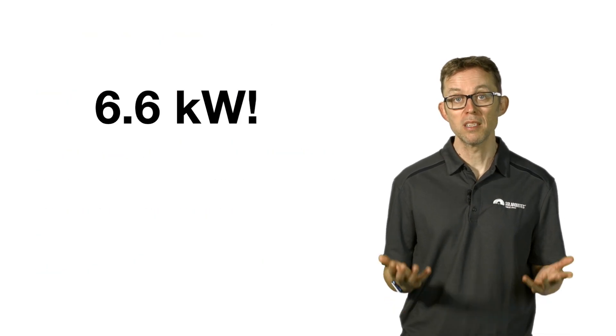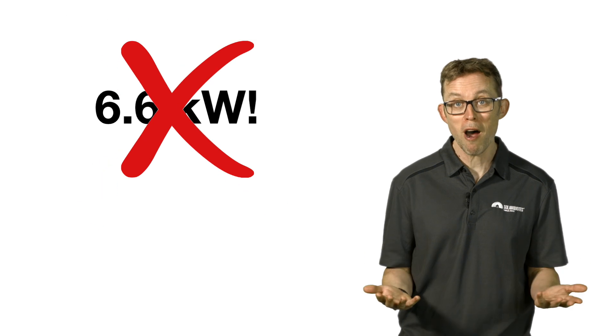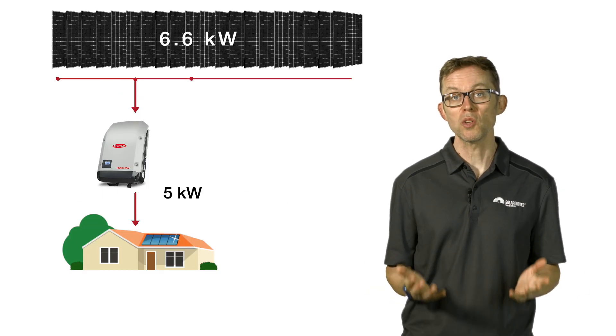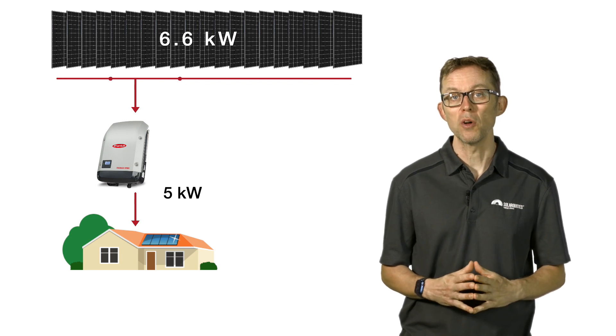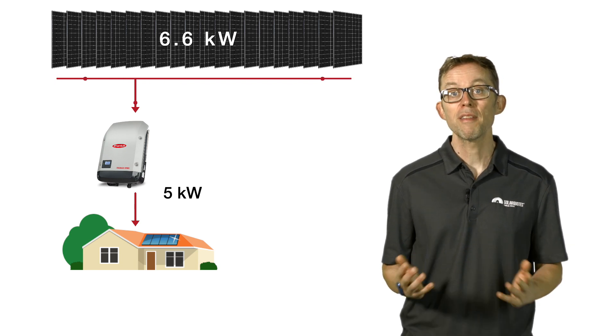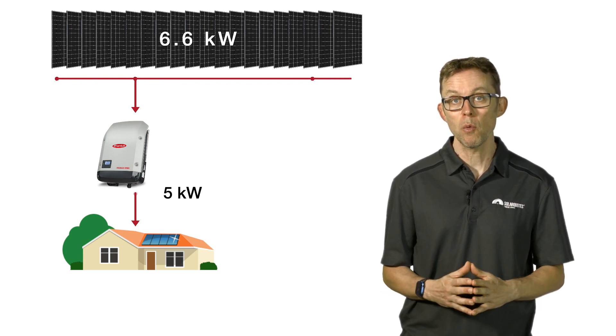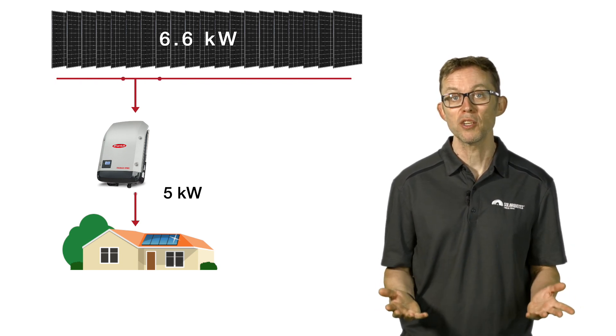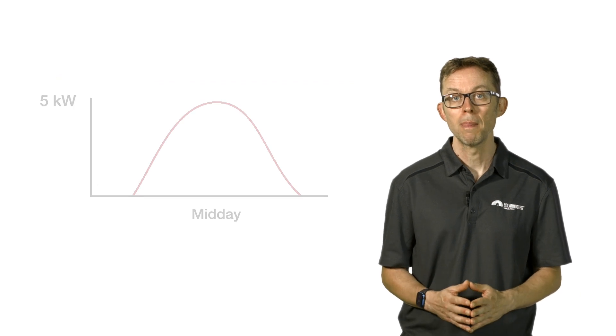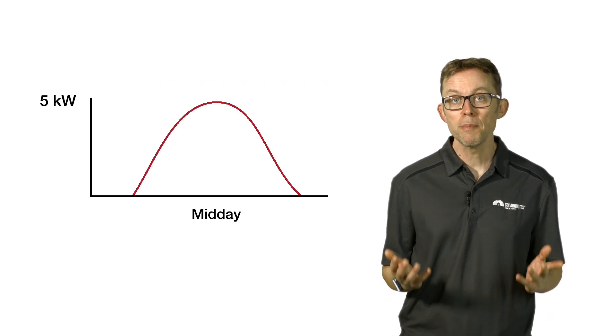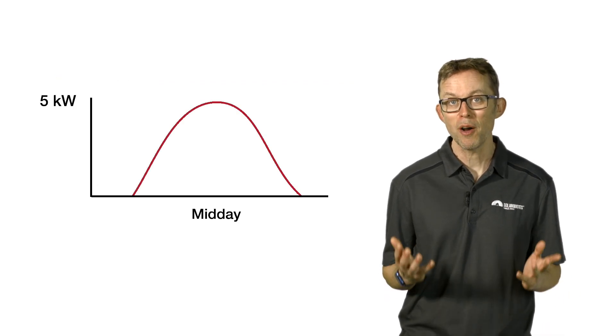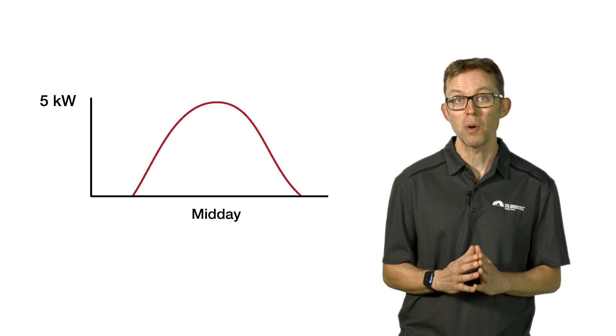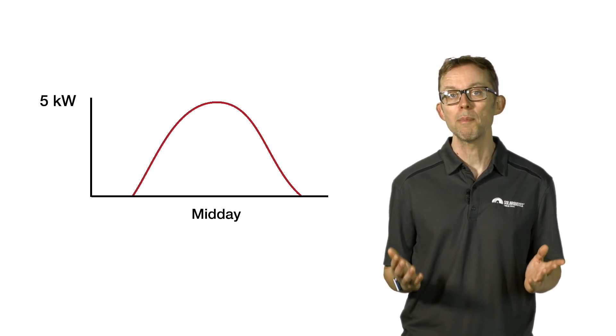6.6 kilowatt solar systems almost always use a 5 kilowatt inverter. That means you'll never get more than 5 kilowatts out of the system at any point in time. You'll only produce your peak power around midday on a perfect solar day, which is a day that is sunny but not too hot, as hot panels are actually less efficient.